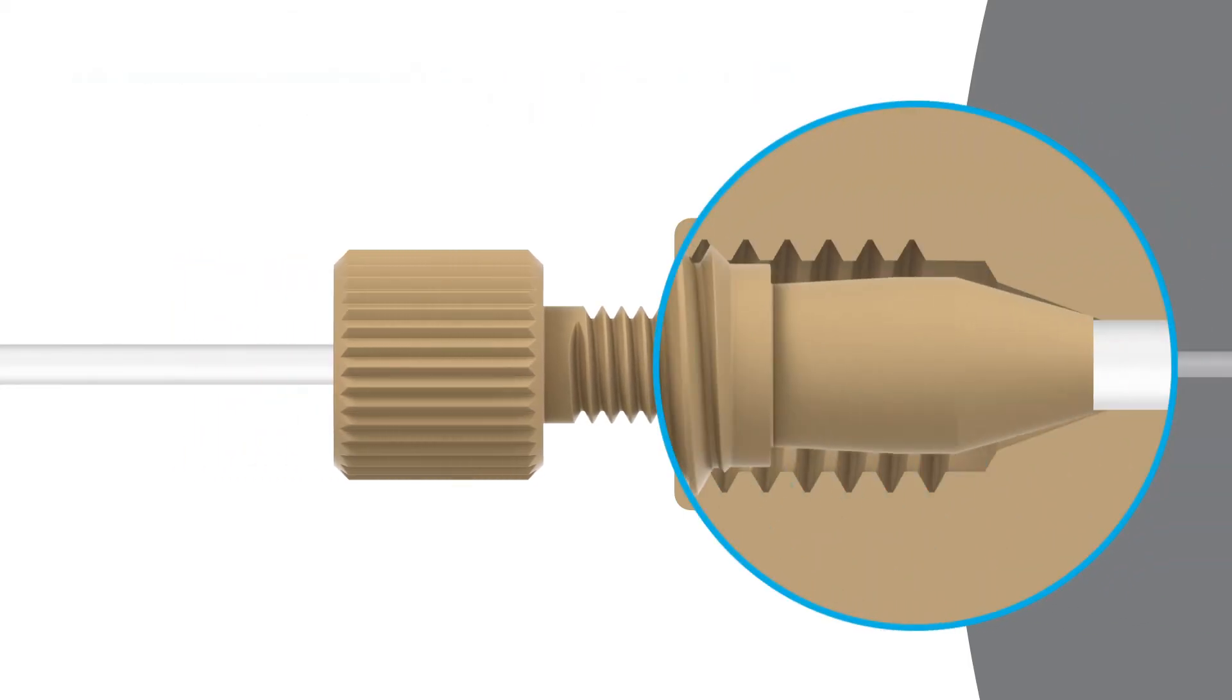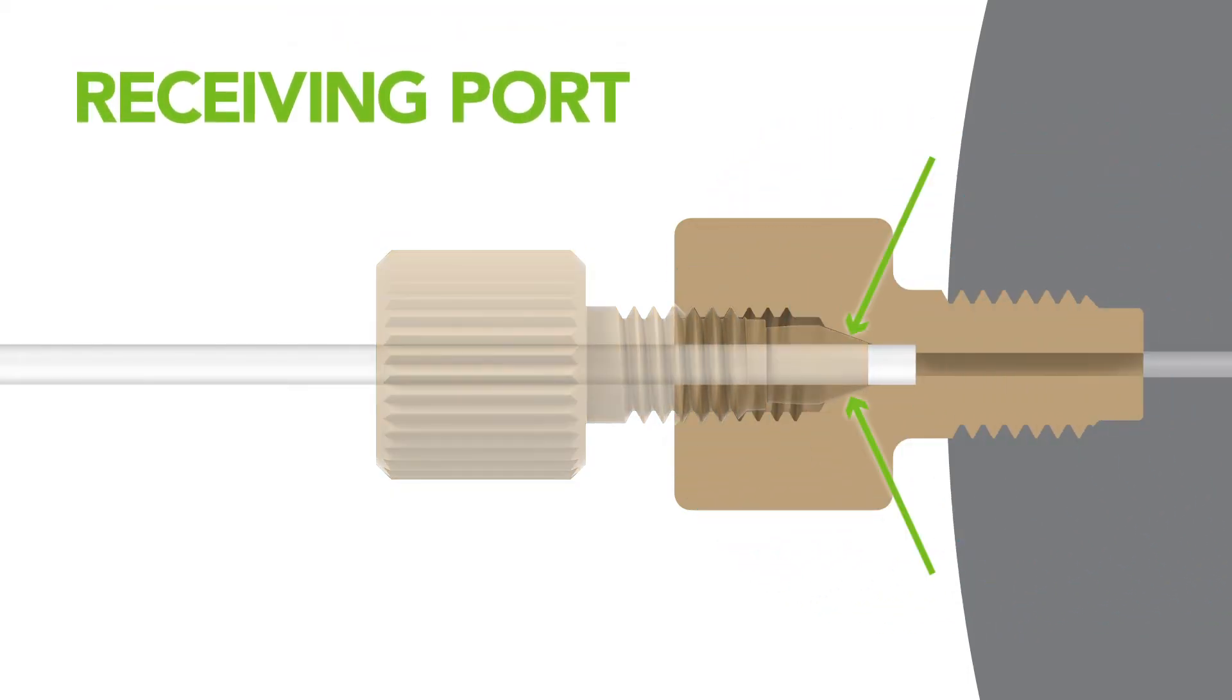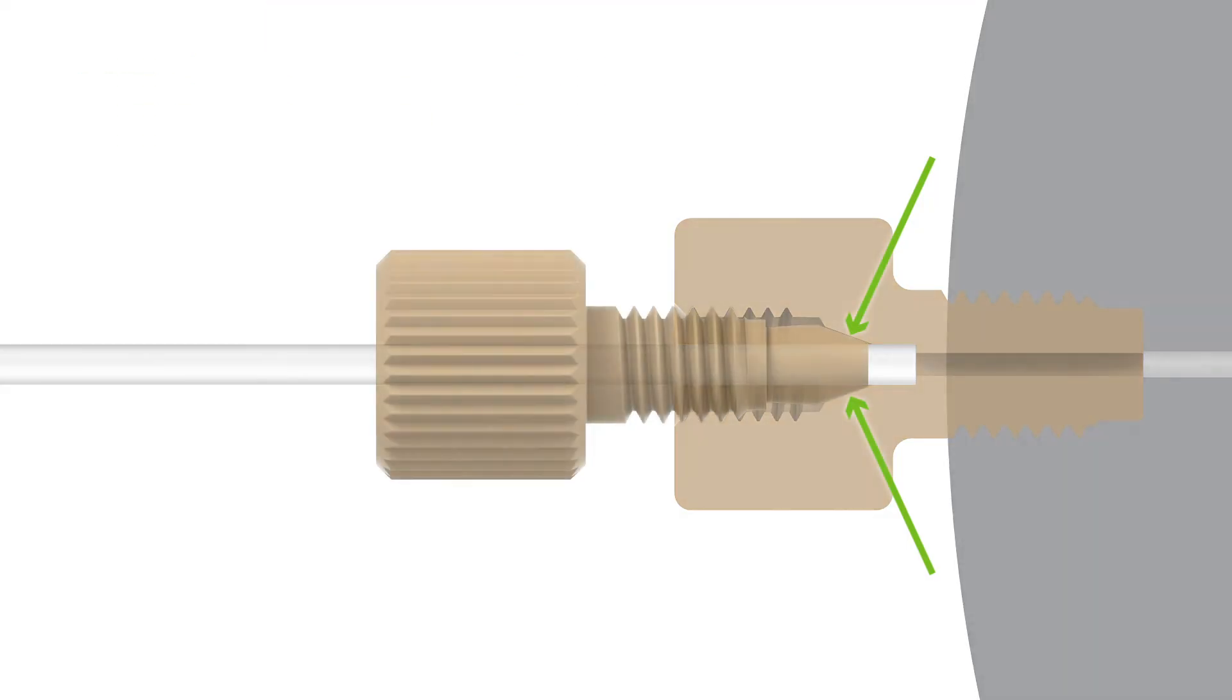The goal is to use a ferrule with a narrower angle than the receiving port, so that when the nut is tightened, the ferrule conforms to the port's angle and compresses against the tubing's wall. For a seal without leaks, the surface of both the receiving port and ferrule must be free of imperfections.